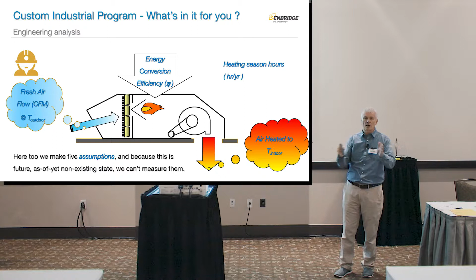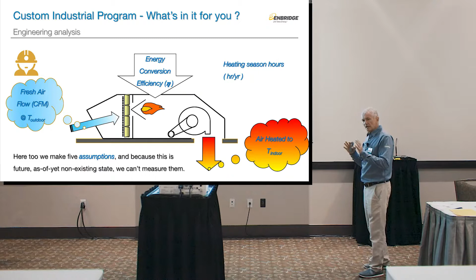It's one thing to say this makeup air unit has to be large enough to handle even the coldest day, and another to say this makeup air unit actually uses this % of energy, because over the course of the year we have the coldest day only 1 day a year. So that's why we have to be able to judge that.